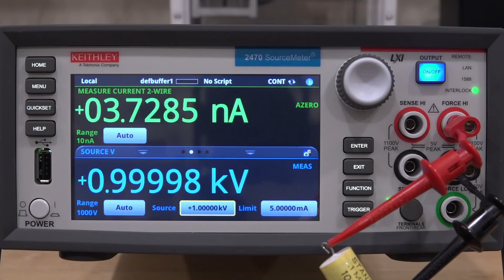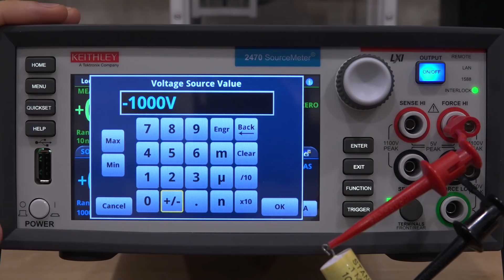But I'm going to do something you normally cannot do with power supplies. In fact, it's often prohibited because it will damage the instrument. But the 2470 is a 1000 volt, 4 quadrant instrument, so I'm going to go from 1000 volts, while the output is enabled live, to minus 1000 volts. That's a 2000 volt differential. As soon as I set this to minus 1000, the instrument will try to apply minus 1000. For a brief moment there will be almost a 2000 volt difference observed at some nodes of the circuit, and yeah, that's a lot. The instrument has to absorb that, because the user can, of course, enter this number if they want to. So let's give it a try.